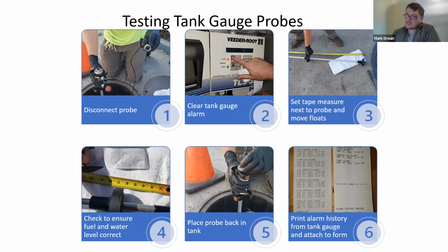So the idea is you disconnect the probe, and at this point your tank gauge will go into an alarm. In this case, it was the Veeder-Root, it went into alarm, right? So we saw that you disconnect it, alarm, we know it's working properly. The next thing you want to do is clean off these floats and move them up and down. So this is what's in your tank, with the product. I think this one, Kevin probably can answer better. I think this is your fuel probe. As you're getting a delivery, you start off at 2,000 gallons and then you go up to 7,000 gallons. This float is what's moving up and communicating with your tank gauge.